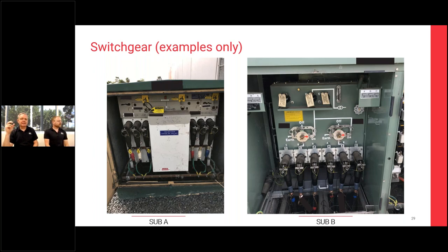So one of the classics is we found PD. It looks like it's internal void because of the TEV signals that Brad is saying. The solid insulation is here. We're on the termination. Let's replace the termination. And maybe 7 or 8 times out of 10, that is actually the right thing to do. But it's always worth really looking into it in a bit more detail to see, is that actually where the source of discharge is?